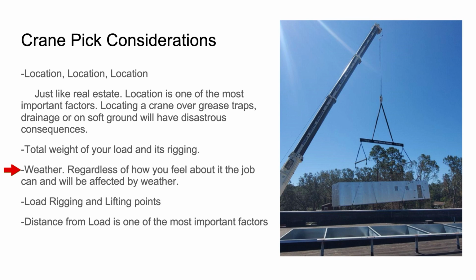And of course, weather is a big factor. You could have a crane out there that costs a lot of money, but you get washed out just based on weather. It's not typically the rain that causes it, but with rain usually comes wind and lightning. Lightning is the biggest factor, aside from wind. Wind will shut down the job. It could be 3 miles an hour where you're standing on the ground, but 17 miles an hour up there. They have to really take that into consideration, because you don't want a 14,000 pound unit blowing around in the wind on top of a crane. It's not safe. So it's something to think about - even though there's pretty good weather before a hurricane, a day and a half out, if you're starting to get weather coming in, don't try to sneak the pick ahead of time, even though it's not lightning or raining yet.